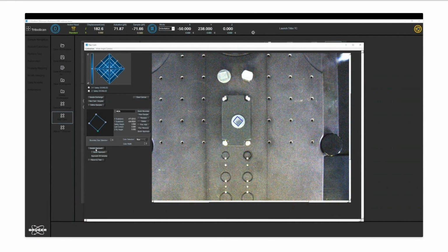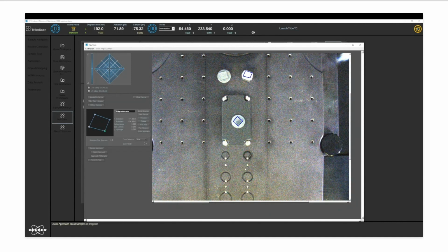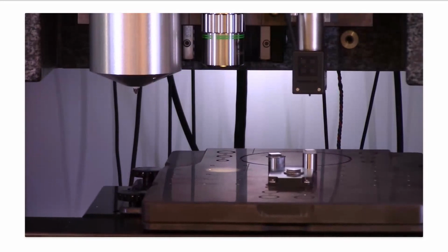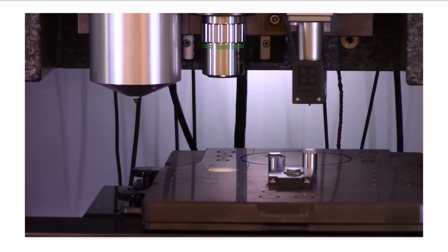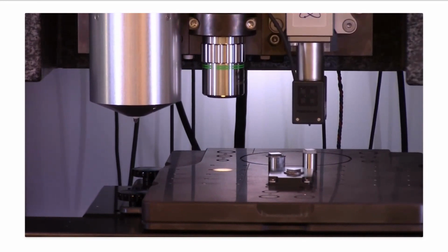Now that all the samples are defined, the system can go ahead and automatically quick approach all of them. You can just pick the tallest sample on the chuck, which is the polycarbonate in this case, and this sets the Z fly height based upon that. This part is going to take a few minutes per sample, but it's going to go through all the samples automatically. We can see here inside the enclosure how the sample stages move for the quick approach of all of these samples that were just defined.